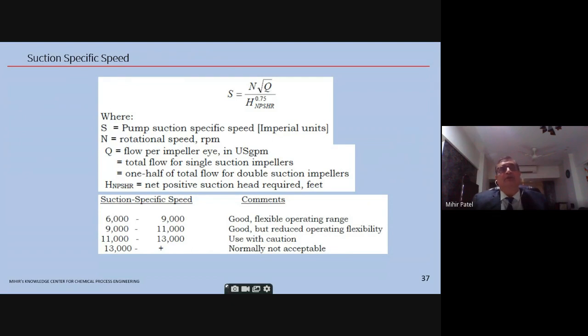I would say go with a conservative value. 7.5 to 8,000 in American units should be the suction specific speed. With that, you can calculate the NPSHR required in case you don't have access to any go-by data or vendor interaction, and you can plan your FEED engineering with that NPSHR, adding 1 meter to get the NPSH available. So here the process engineer can use this formula as a last resort.